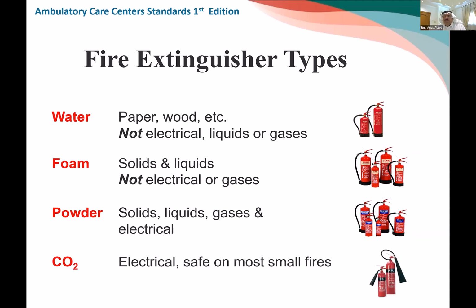This is only used for electrical safe on most small fires, but you need to make sure the ratio is there. Most of your extinguishers should be powder, because that's the normal one. We use carbon dioxide only on critical electrical rooms, high equipment, MRI, CT. If you have an X-ray machine, you will put one carbon dioxide extinguisher only there. Carbon dioxide should only be used on electrical fires if they are energized. If the equipment is energized, you can use carbon dioxide. If there is a fire and there's no power, you can use powder on it, there's no issue.